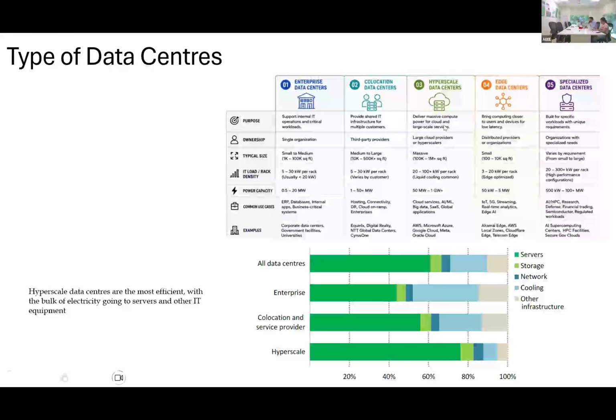But now hyperscaler data centers are increasing. This graph shows energy consumption distribution in typical data centers. In enterprises, cooling is about 30 to 40% of total data center energy consumption, whereas in co-location it's in the range of 25-30%. But in hyperscalers, the percentage of cooling is very low, in the range of 10 to 15% only, while server energy consumption is very high.